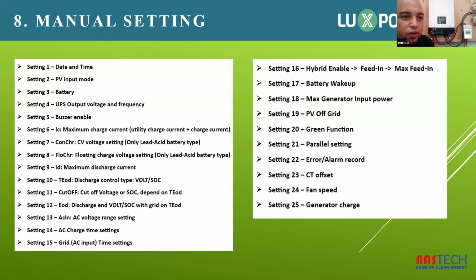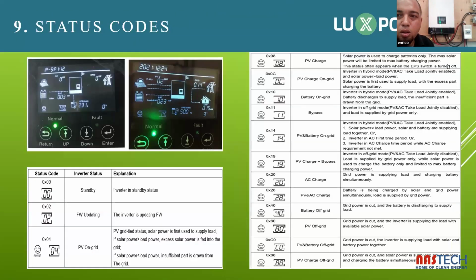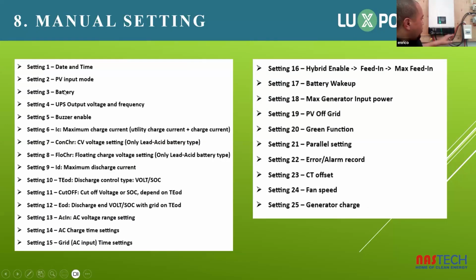when you're completely off grid, no internet, you go onto the inverter and give it battery power. Firstly, you need to power up the inverter. So you put the battery power on the inverter. Once there's battery power on the inverter, you hold in enter. You'll get the spanner icon in the corner, and you will start toggling between all those settings. The first setting we'll look at is the time and date, making sure that your time and date is correct.